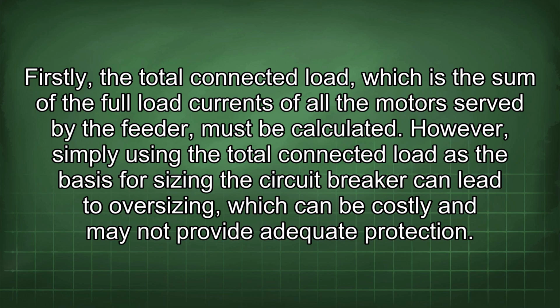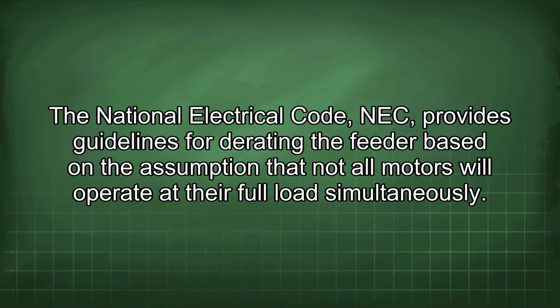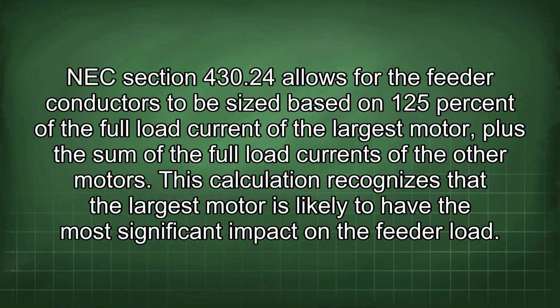However, simply using the total connected load as the basis for sizing the circuit breaker can lead to oversizing, which can be costly and may not provide adequate protection. The National Electrical Code (NEC) provides guidelines for derating the feeder based on the assumption that not all motors will operate at their full load simultaneously. NEC Section 430.24 allows for the feeder conductors to be sized based on 125% of the full load current of the largest motor, plus the sum of the full load currents of the other motors. This calculation recognizes that the largest motor is likely to have the most significant impact on the feeder load.